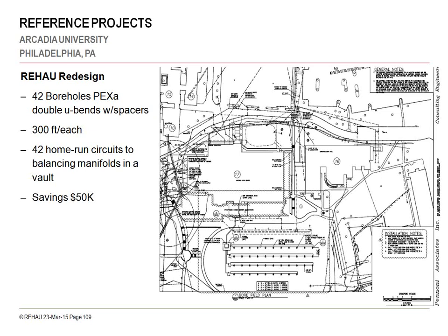Going down, you can see on the left of the field there, kind of the northwest corner, that's the vault. And we had those commercial grade balancing manifolds inside that vault, 3 sets of them, a set along each of the long wall of the vault and one on the back side of the vault. Those being tied together, and then we had 6-inch mains coming out of the vault, a single 6-inch supply and return for the vault going back into the mechanical room. So you had the ability now, if ever needed, to access into the manhole cover of the vault, which was located about 18 inches down below grade with a blue ball, so you could locate that manhole cover.